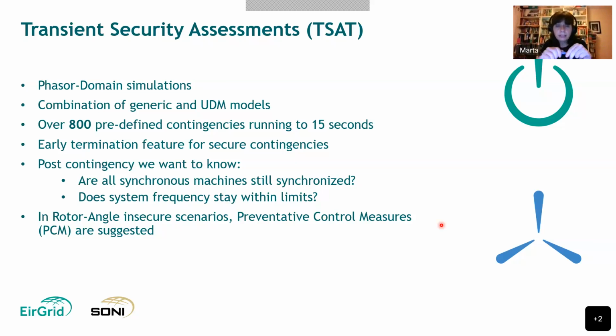We run a series of contingencies that are defined and live within the DSA environment. Currently we're running about 800 of those contingencies, and they run up to 15 seconds. This is computationally intensive, so we have some features which identify whether the case is secure by looking at the rotor angles. If after a couple of seconds it's identified that the distance between the angles is not increasing, it deems the contingency secure and doesn't run out the full 15 seconds. This efficiency allows us to run this level of contingencies.